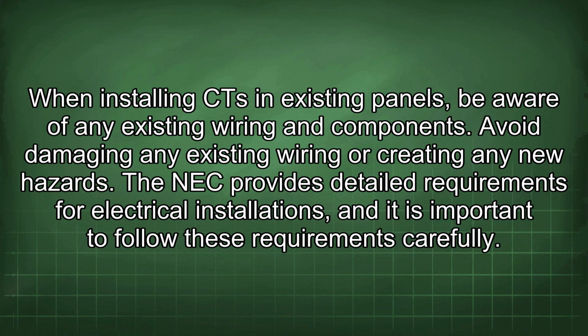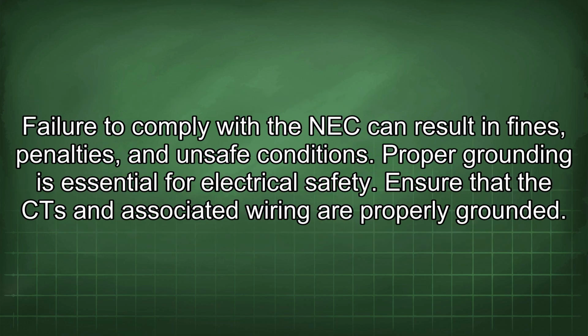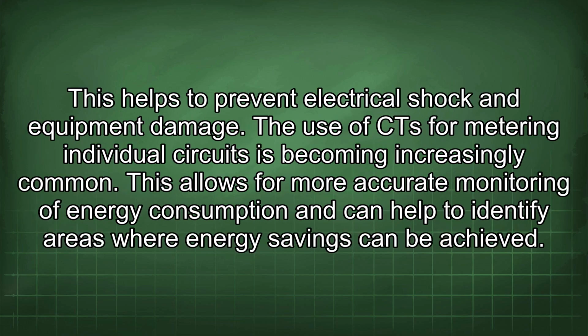When installing CT in existing panels, be aware of any existing wiring and components. Avoid damaging any existing wiring or creating any new hazards. The NEC provides detailed requirements for electrical installations, and it is important to follow these requirements carefully. Failure to comply with the NEC can result in fines, penalties, and unsafe conditions. Proper grounding is essential for electrical safety. Ensure that the CT and associated wiring are properly grounded. This helps to prevent electrical shock and equipment damage.